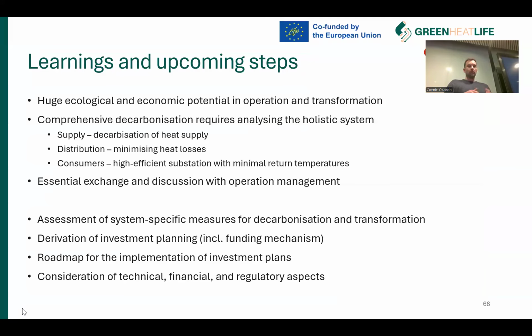With these three networks and scenarios I've shown you, we are focusing on supply decarbonization, for example heat pump integration. We focused on distribution, to increase efficiency through temperature reduction. And we are also focusing on the consumers, identifying that there is huge potential when we handle the faults currently present in the substations of the consumers, reaching very low return temperatures there.